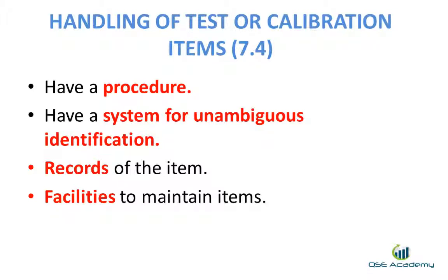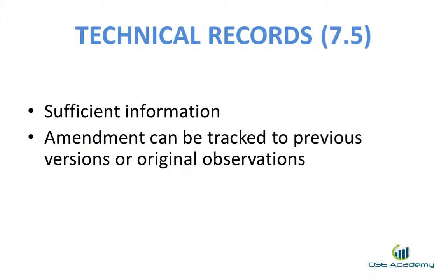7.5. Technical records. The laboratory shall ensure that technical records for each laboratory activity contain the results, report, and sufficient information to facilitate, if possible, identification of factors affecting the measurement result and its associated measurement uncertainty, and enable the repetition of the laboratory activity under conditions as close as possible to the original. The technical records shall include the date and the identity of the personnel responsible for each laboratory activity and for checking data and results.